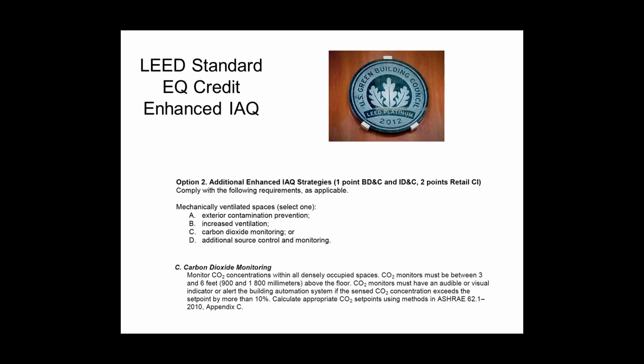And then the last thing on the CO2 discussion comes up on LEED type projects. One of the indoor air quality points that you can achieve in the LEED standards can be achieved by doing carbon dioxide monitoring in the space. As I mentioned before, you are not allowed to do it in the return duct. It has to be in the space, specifically between 3 and 6 feet above the floor. I suppose if your return duct was on the wall at 5 feet, you could probably get away with saying that, but generally speaking, it's got to be wall mounted.